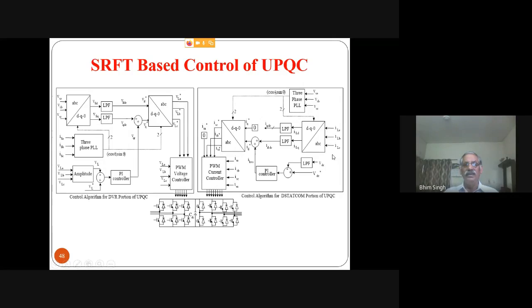Typically, you will find the second harmonic on the DC-link here. Even if you have a three-phase system, you may have a second harmonic, because there may be either an unbalance in load current or an unbalance in the voltage, or both. You will get a second harmonic. That's the reason you have to put a low pass filter here. Otherwise, it may be the second, then it may be the sixth harmonic. This depends on the nature of the system.